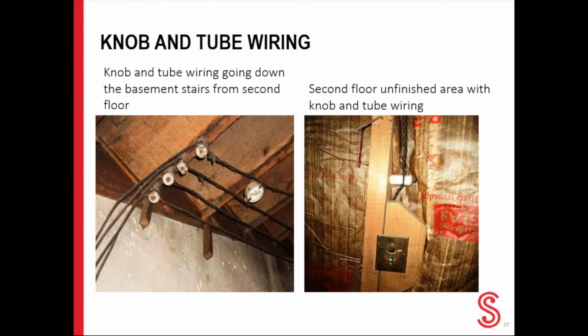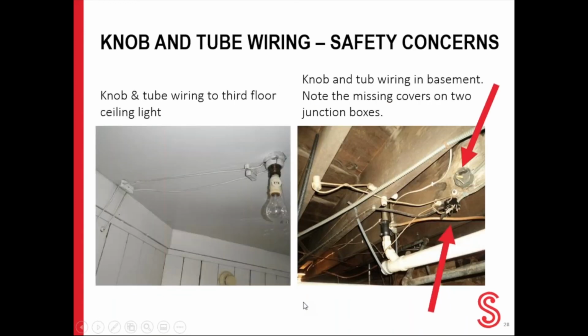This system was used mainly from the 1880s up until the 1940s. It's an old two-conductor wiring method that consists of hot and neutral wires separated from each other. The knobs are ceramic and connected to the frame construction to hold the conductors in place, and the tubes are also ceramic and run through the framing members to protect the conductors. So there are obviously safety concerns with this too.